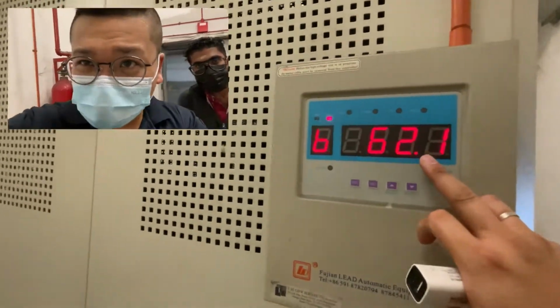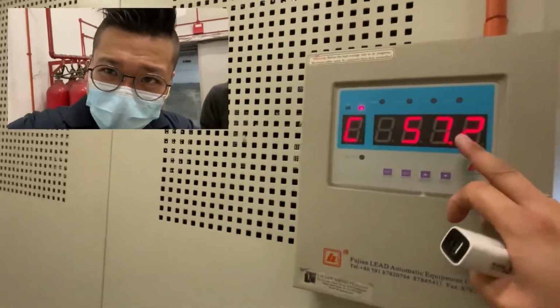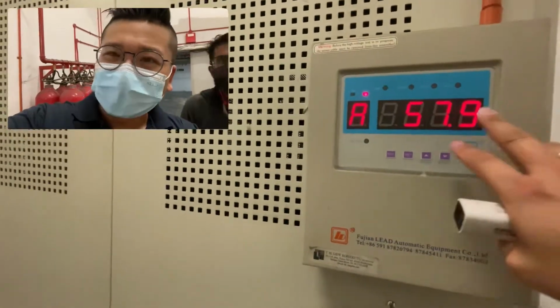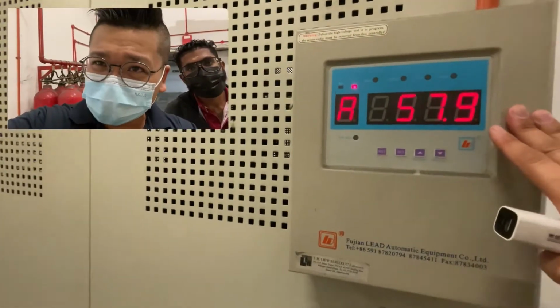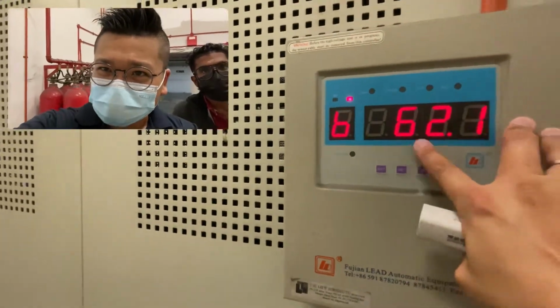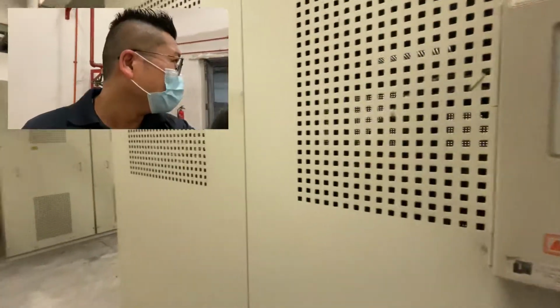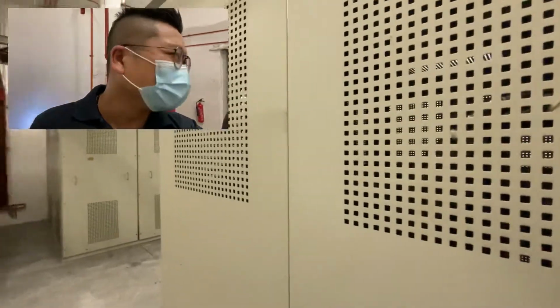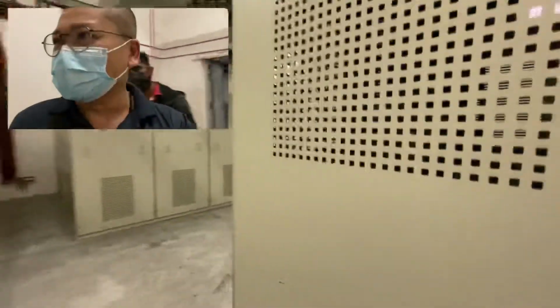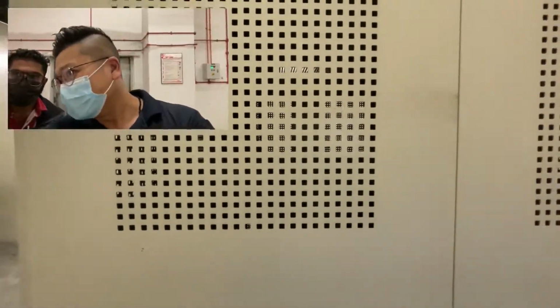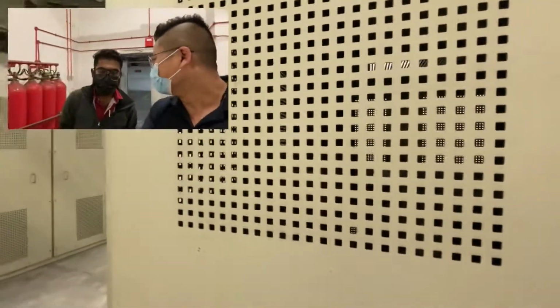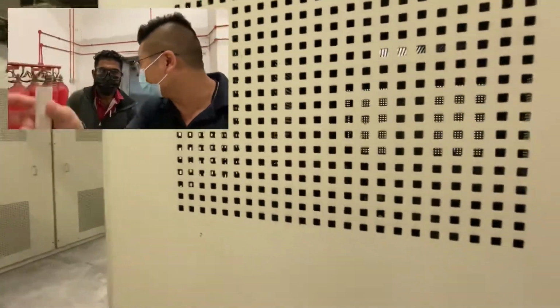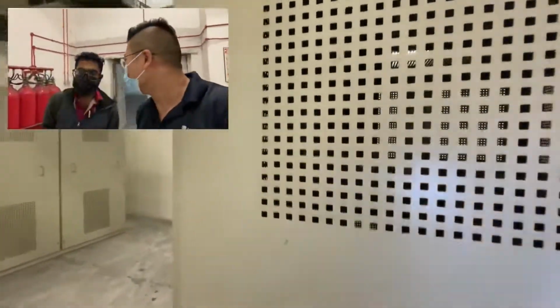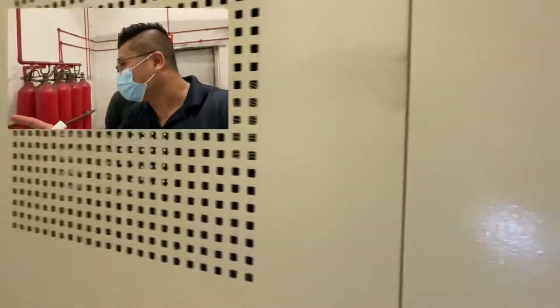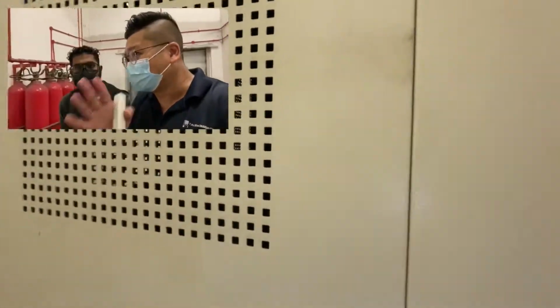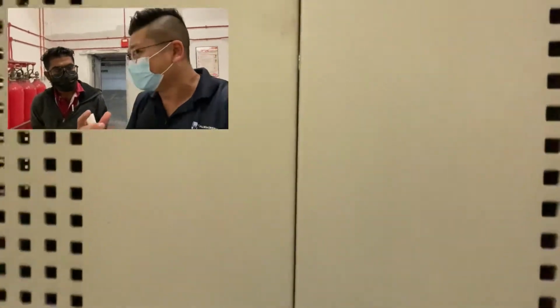A is the red phase, B is the yellow phase, and C is the blue phase. So normally we take the yellow phase as a reference because it's located at the middle of the core. It's the most warm, most highest. Because the transformer is 1, 2, 3. The center core is the most warm one. So we will take the temperature at the center as a reference for the overall transformer. So if they say, how I know this transformer is performing, is it hot or not hot? By referring to B.